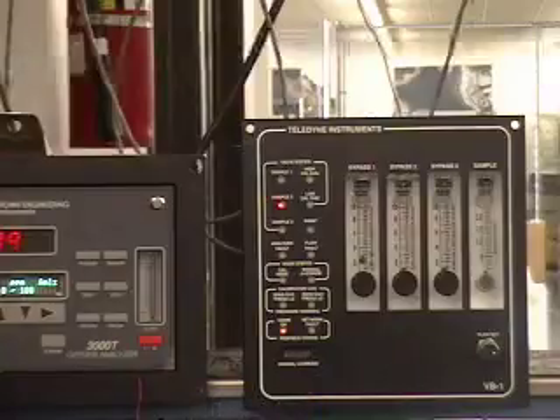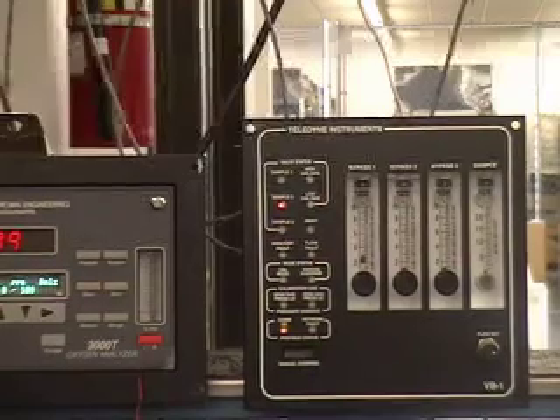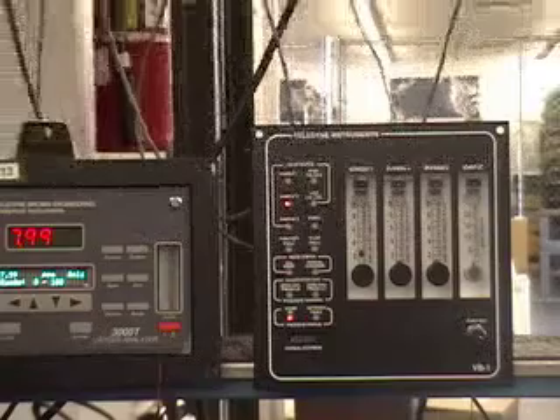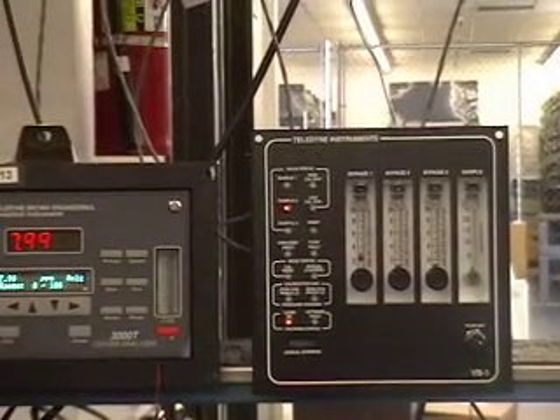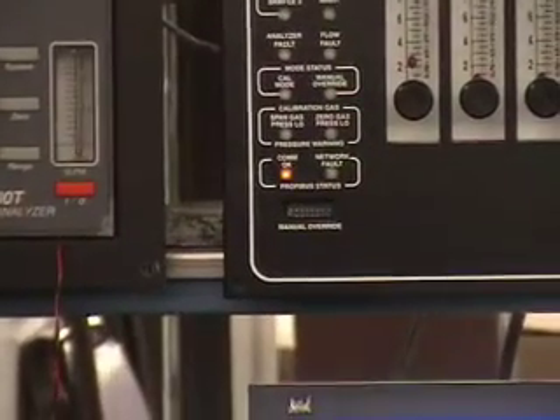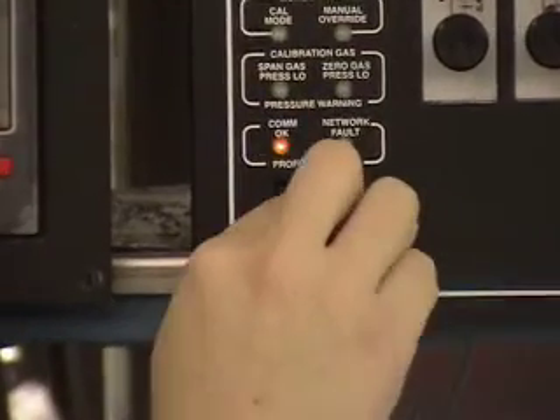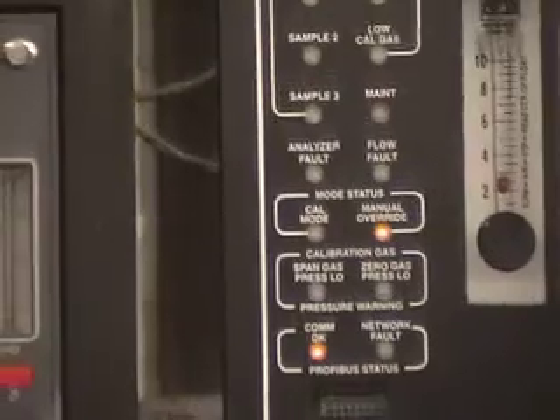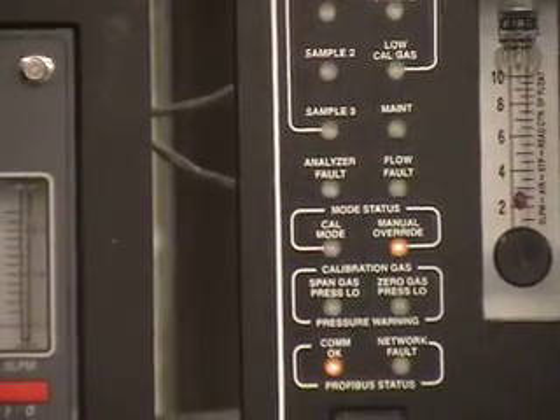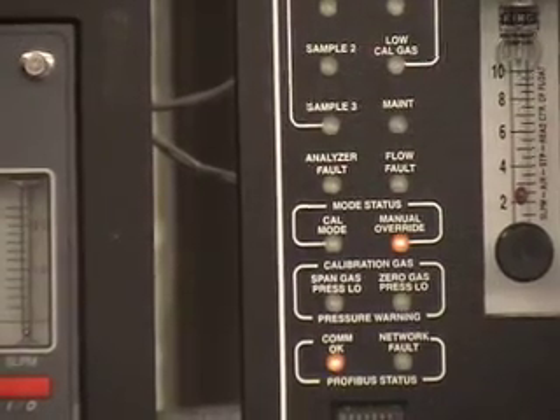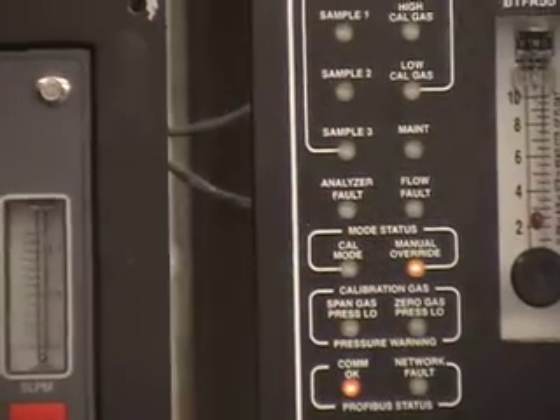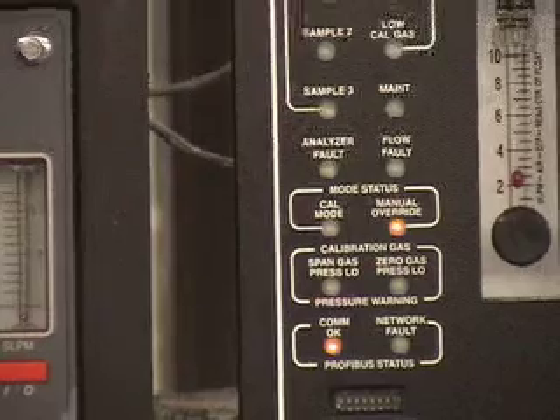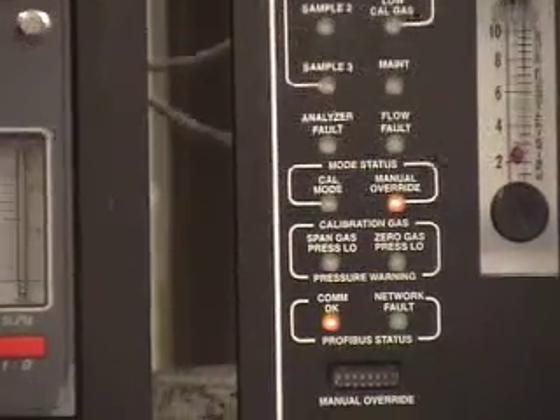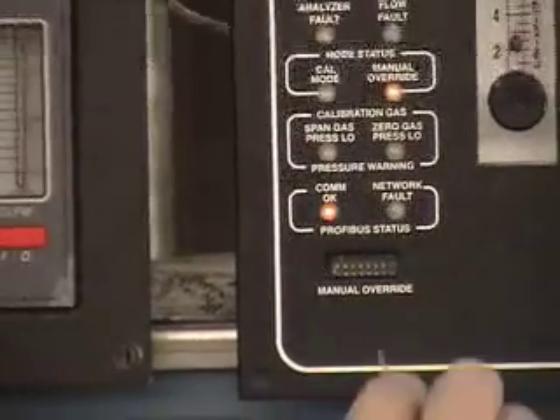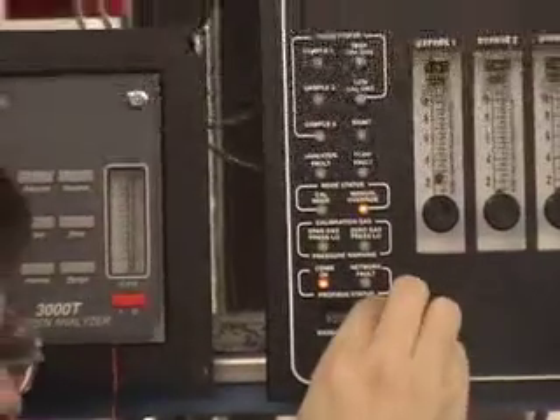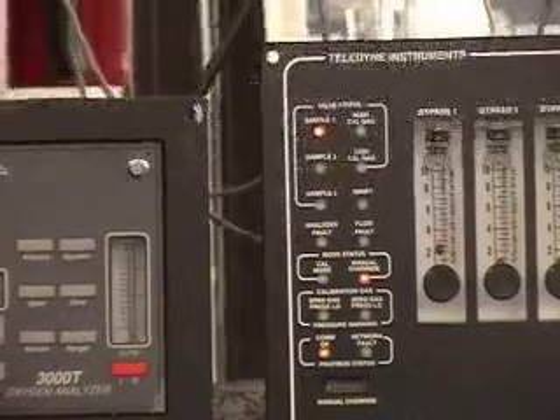Now, we can go into the manual override. To set the instrument in manual override, we go to these DIP switches over here. The rightmost DIP switch, position number 8. If I pull it up, you will see the manual override light come on. That means now I have control of the valve through the front. And you can see no valve is open right now because all the switches are down. I will control the valve through the DIP switches over here. So, if I want to turn on sample 1, I can turn on position number 7, the second rightmost. There, we can open the valve from the front.